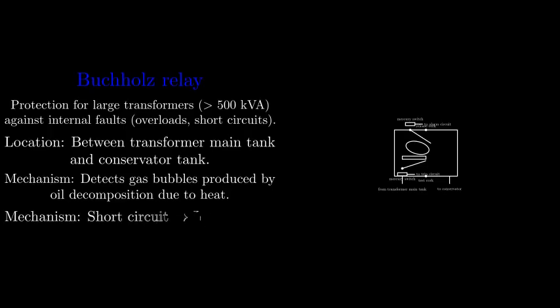Now, what about a more serious fault, like a short circuit? A short circuit produces a very large volume of gas very quickly. This causes a sudden rush of oil into the relay chamber. This oil surge lifts a flap, which activates a second mercury switch. This switch is connected to the tripping circuit, and it immediately disconnects the transformer from the power supply, preventing further damage. The Buchholz relay is a crucial safety device, providing early detection and protection against internal transformer faults.